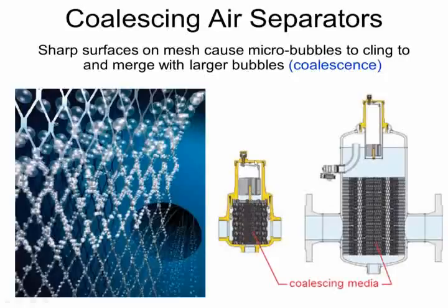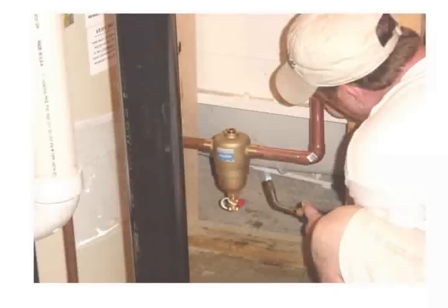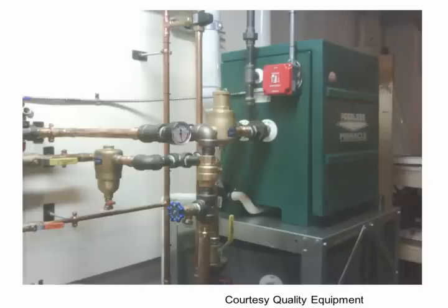Now, before I leave this slide, you can see these little pins here. Our floats are pinned because it's not always very easy to make sure that the air separator is perfectly vertical. So if your flanges are a little bit rotated and as a result you're not perfectly vertical, that's okay, because the Caleffi air vent riding up and down that pin keeps it from getting hung up. Because if that pin gets hung up, the air separator doesn't work. So that's a nice feature of the Caleffi air separators.